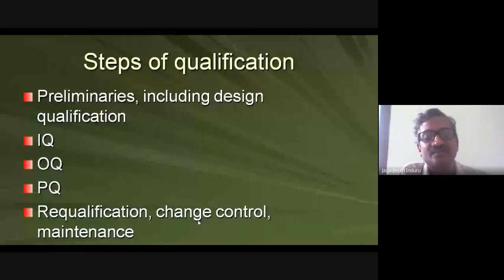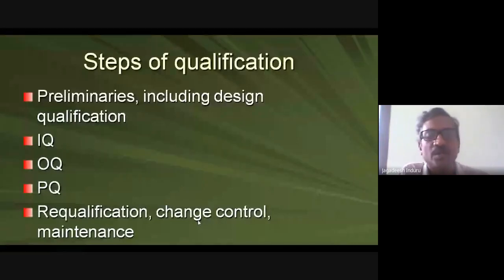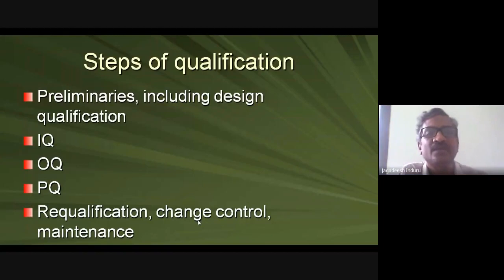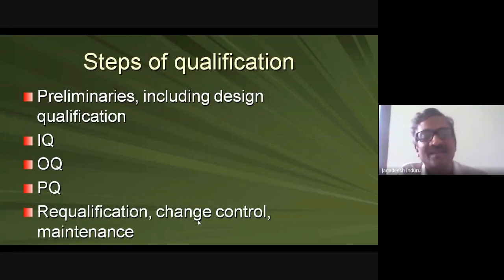Maintenance has already been covered separately in industrial management, so it will not be repeated here. Change control is managed by writing SOPs, approaches, and forms to maintain the status of the validation and qualification process. Most of the time in industry, equipment qualification and equipment validation are used interchangeably — don't get confused. Validation of equipment means IQ, OQ, and PQ.